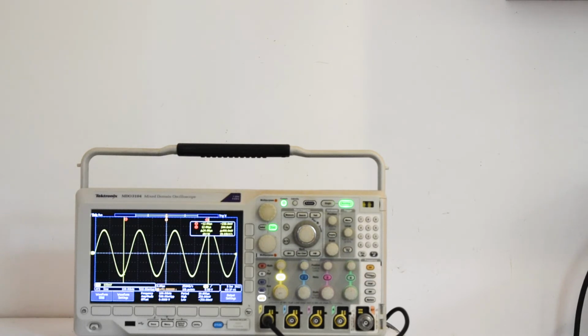At the beginning of the second to bottom readout, the horizontal position scale readout shows on the top line the horizontal scale, which can be adjusted by means of the horizontal scale knob. With delay mode on, the bottom line shows the time from the T symbol to the expansion point icon, which can be adjusted by means of the horizontal position knob.